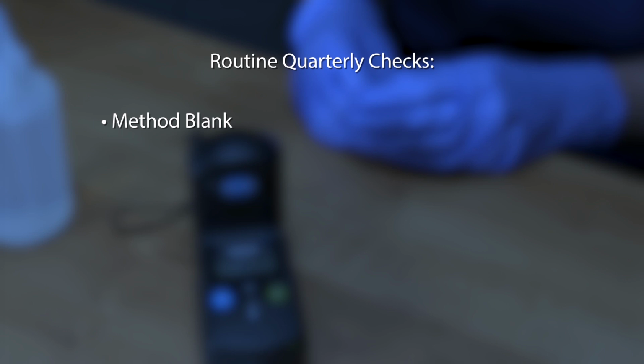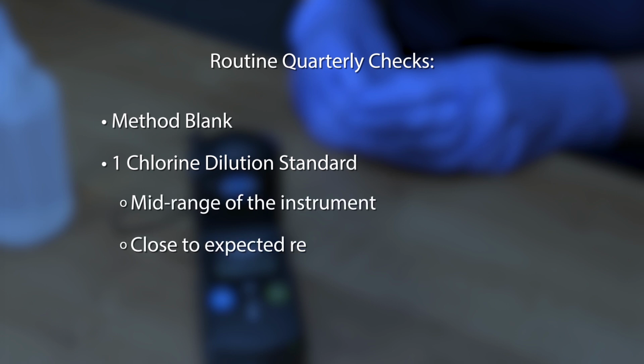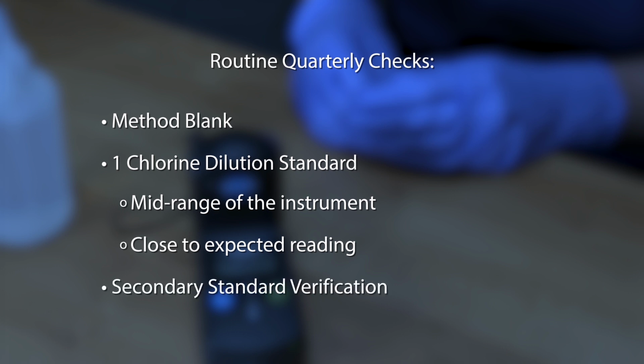Second, perform a calibration verification check using one chlorine dilution standard having a concentration near the mid-range or near the expected concentration in the field. Determine which concentration is appropriate for your water system and instrument, and review the video sections titled Chlorine Dilution Standard Preparation and Measurement, which were discussed previously. When performing your calculation, replace C-want with the real concentration that is appropriate for your water system and instrument. Third, perform a verification using secondary gel standards. Since we have not yet discussed this procedure, let's talk about that now.